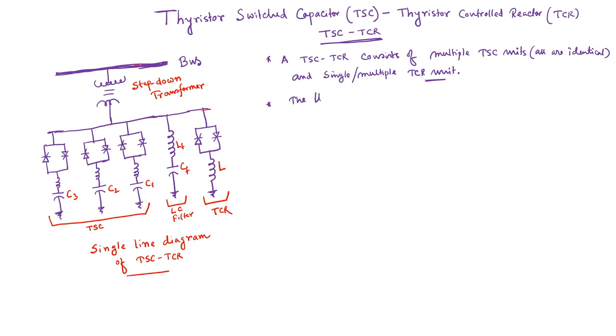Now, the thumb rule is to select n identical TSC units and 1 TCR unit. As I said, the number of TCR units is kept less, so that the total harmonic generation would be less, because one of the major bottlenecks of the operation of TCR, as you know, is harmonic generation.